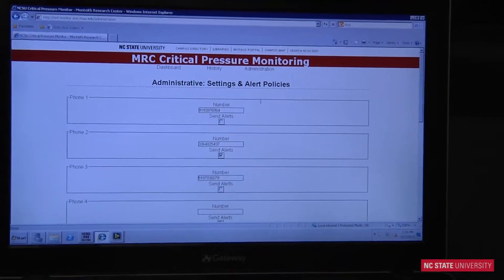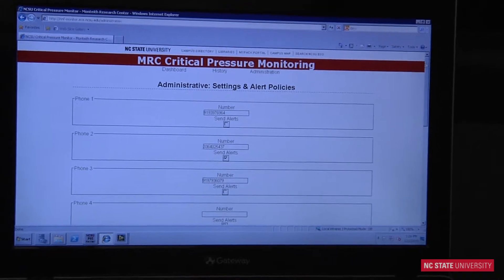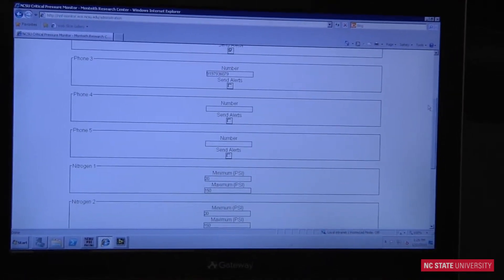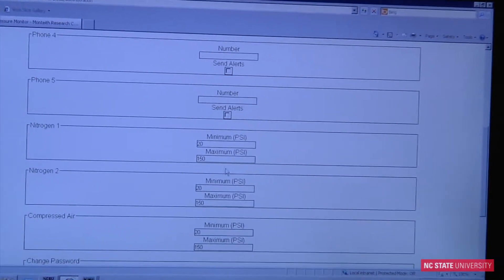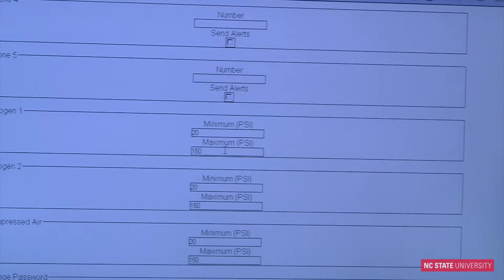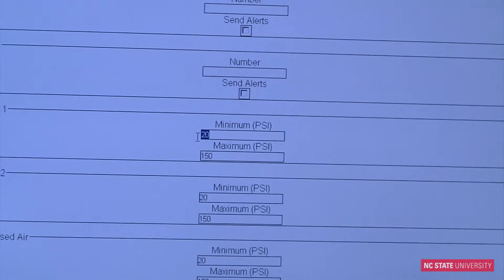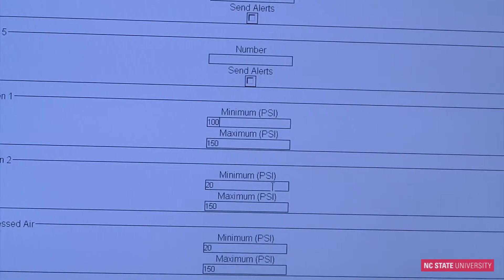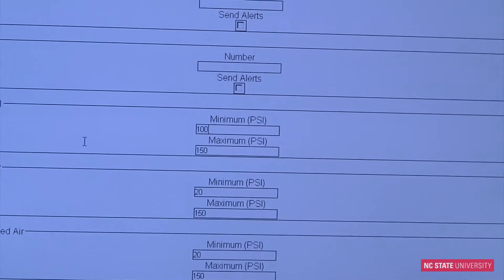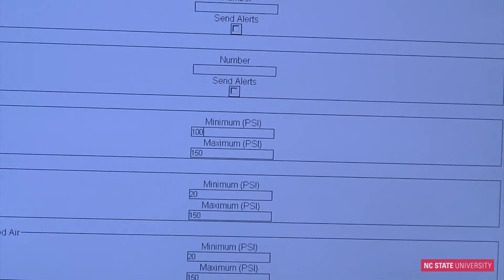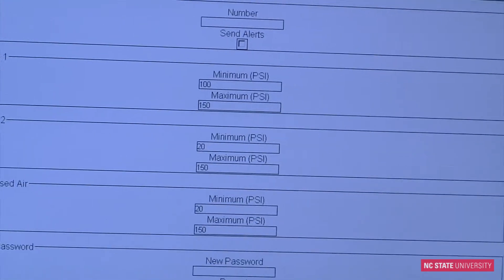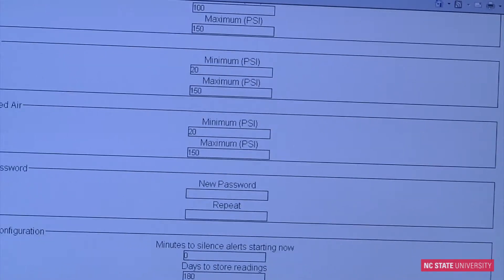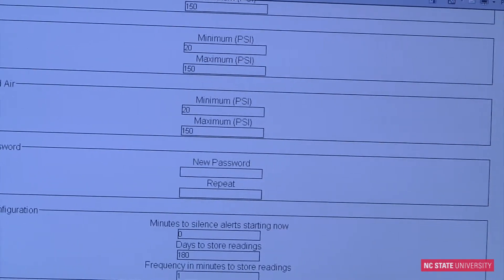Basically, you can set the threshold ranges for each of the pressures we're monitoring. We're going to set one out of range so it will generate a text alert. I'm just going to change the minimum pressure to 100 for this nitrogen-1 tank. And let me save that setting.